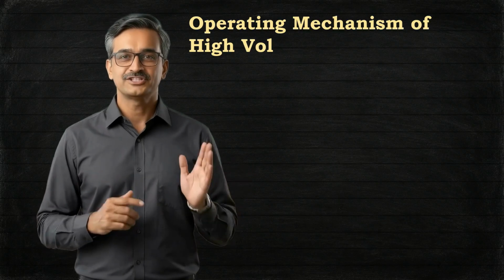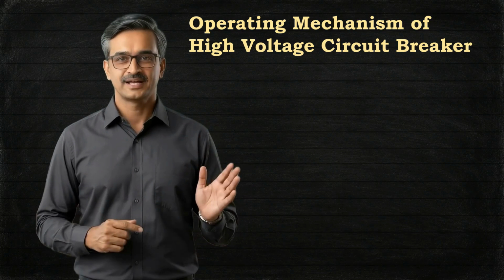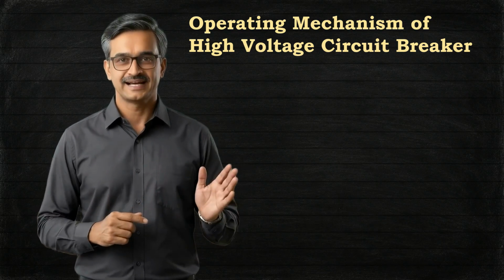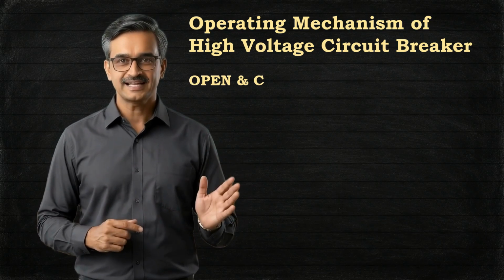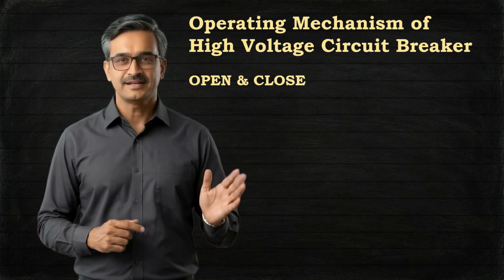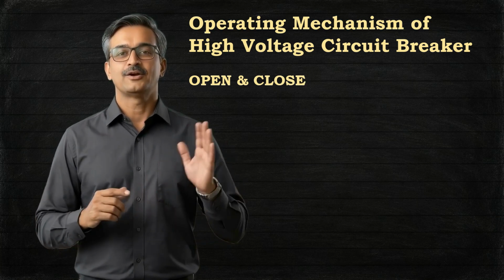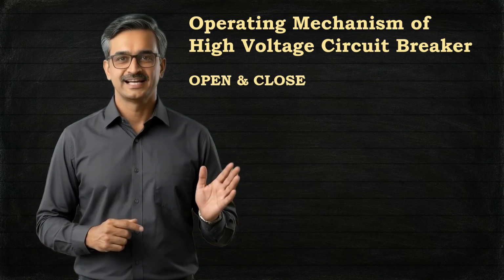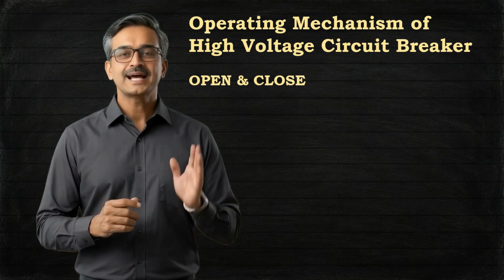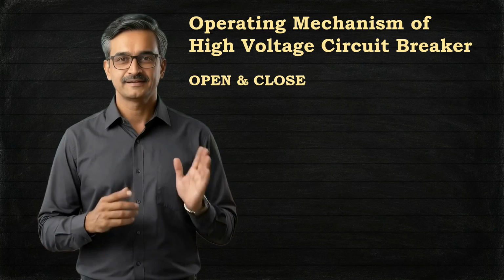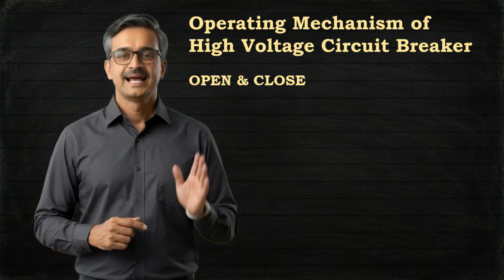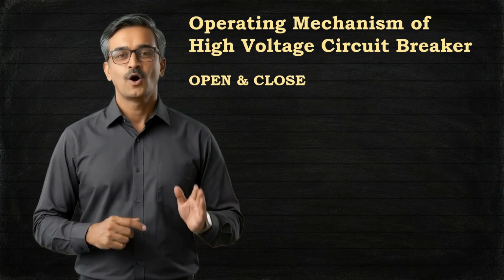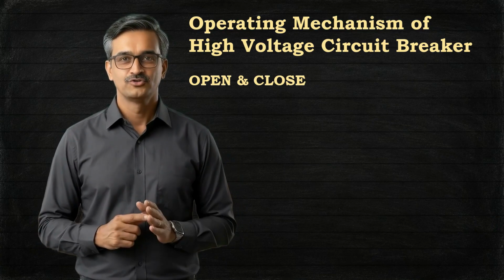We are going to discuss the operating mechanisms of high-voltage circuit breakers. A circuit breaker performs only two operations. It either opens or closes. That's all. But now think for a moment. A high-voltage circuit breaker is not like the switch in your house. Inside a circuit breaker, the moving contacts are made of heavy metallic parts. Along with the contacts, many mechanical links, insulating rods, and operating levers also have to move together.